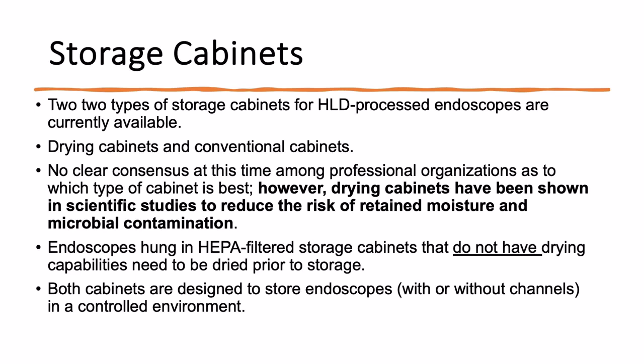Now, there's no clear consensus right now as to which type is best. However, a true drying cabinet has been shown in scientific studies to reduce the risk of retained moisture and microbial contamination. Endoscopes hung in HEPA-filtered storage cabinets that do not have drying capabilities need to make sure that the endoscope is completely dried prior to storage.